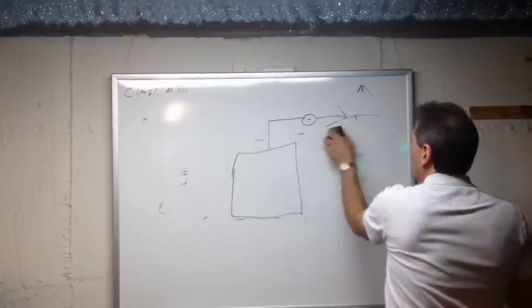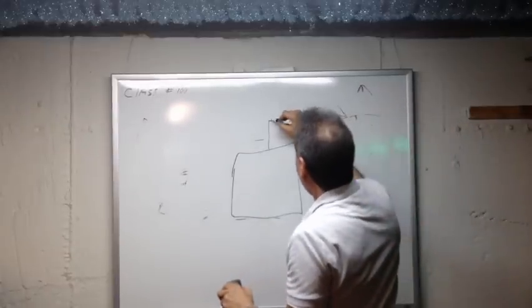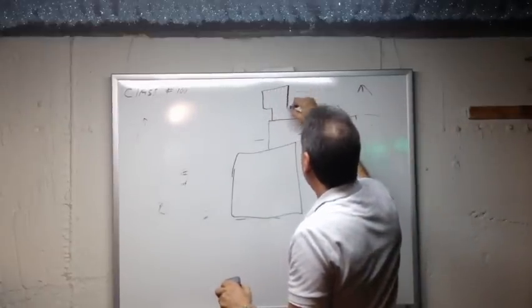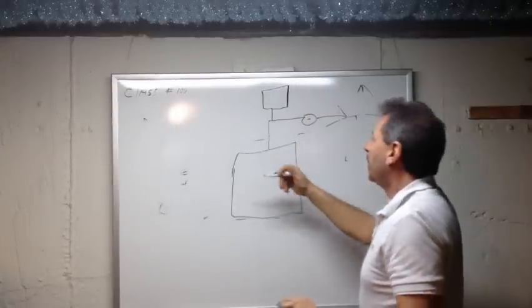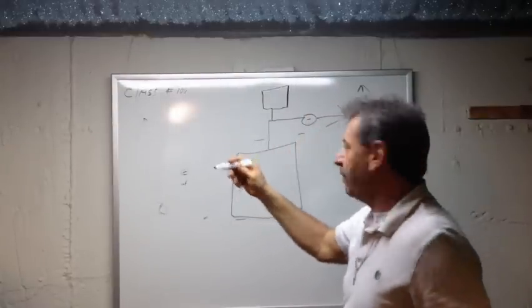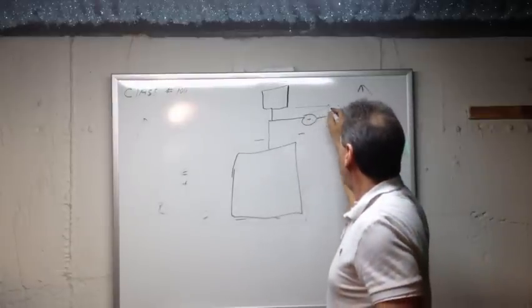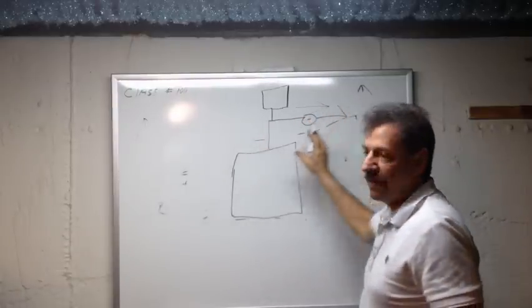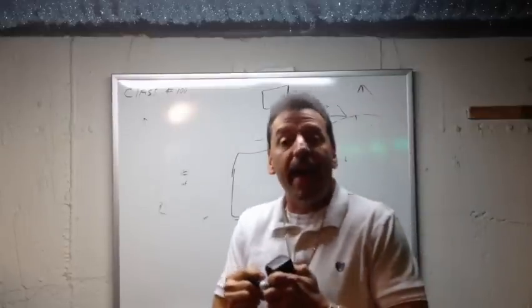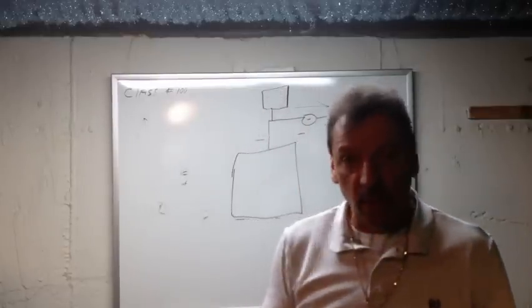But if the expansion tank is tied in anywhere after the circulator, after the pump, after the circulator pump, it'll cause that relief valve to drip water also. That has to be taken out and installed behind the circulator pump, anywhere behind it, on the boiler, on the system. They have to be behind the pump. The pump is going that way. The expansion tank has to be installed behind it. Once it's installed in front of it, again, you're going to get that pressure relief valve leaking water. That's another scenario that people don't know about.